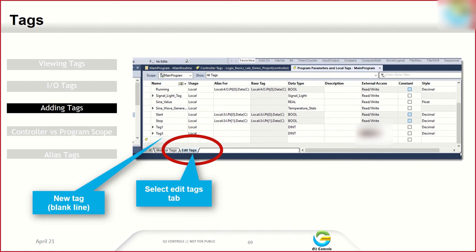But you can change that tag data type before you use that data. If you are using that tag in a move instruction or whatever instruction, and you change the data type, it will create some error message on that particular routine. You can change the description and alias anytime, but the data type you should decide before, otherwise it will create an error. Then you need to find that error and resolve it, and then your tag will work. You can change it, but change the data type only when it is really required.